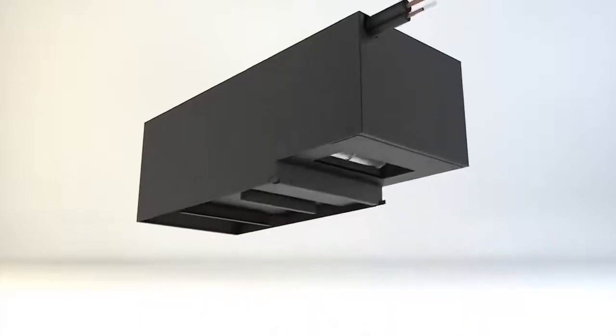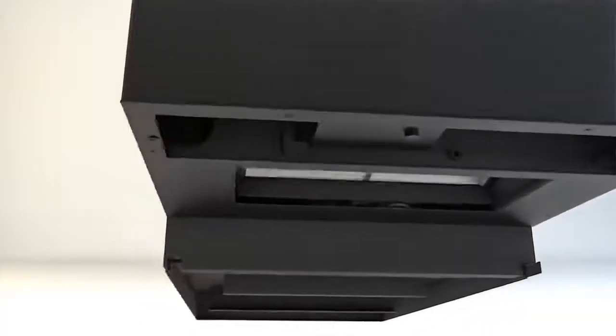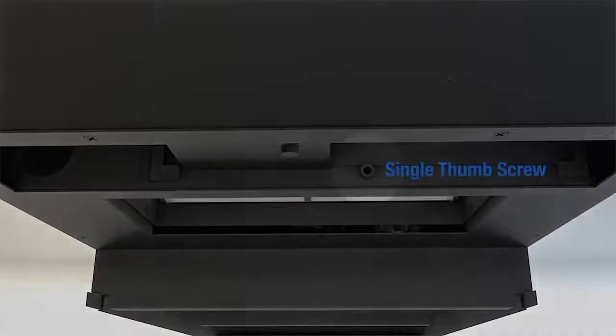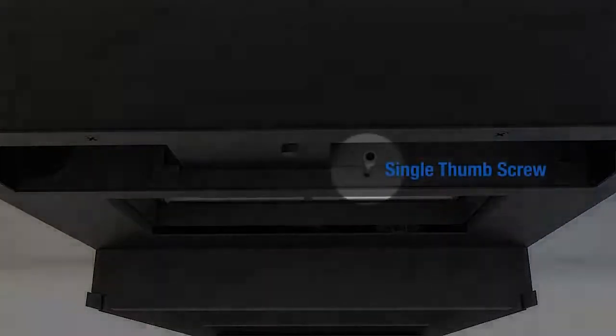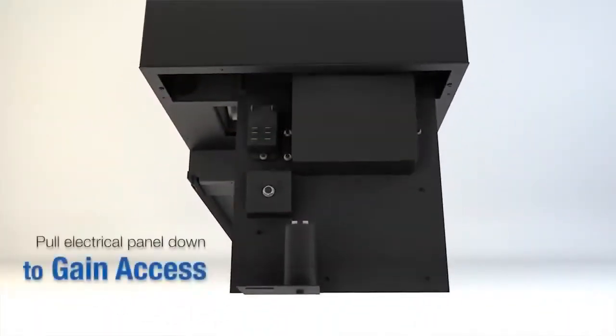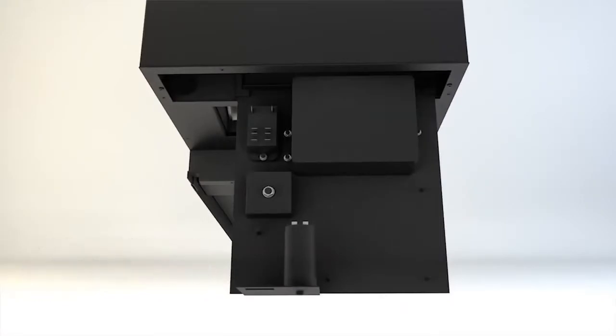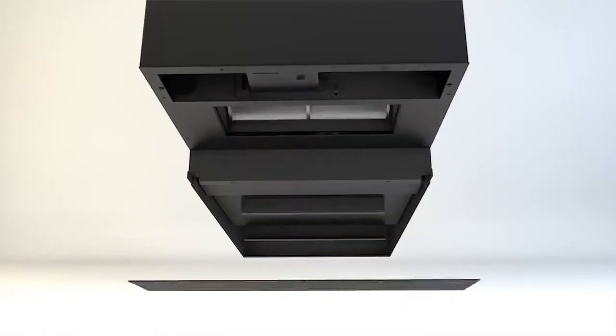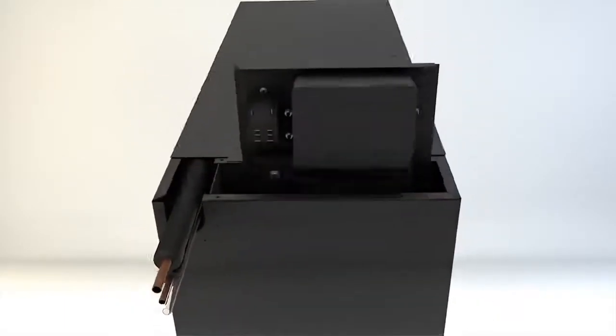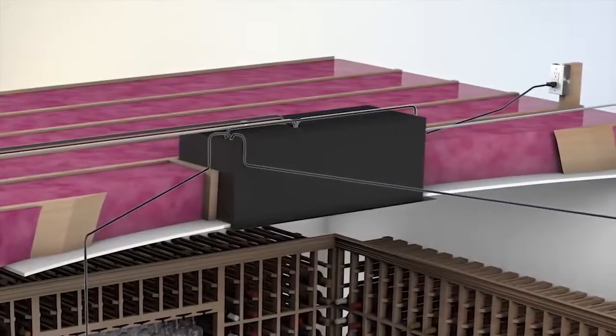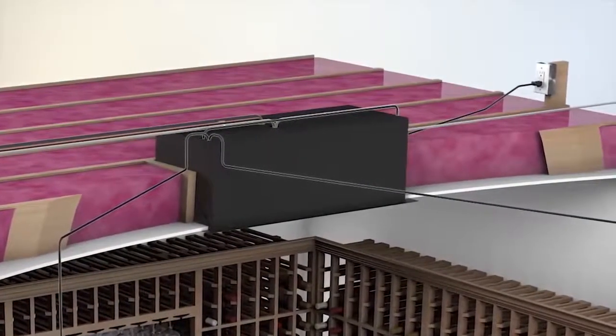For access from the bottom, remove the grille. The electrical panel is held in place by a single thumb screw. Remove the thumb screw and pull the electrical panel out to gain access to attach the electrical source, the thermostat, and the bottle probe. For access from the top, remove the screws and pull out the electrical panel. Use the punch-out panels most conveniently located to feed the lines into the unit and attach.